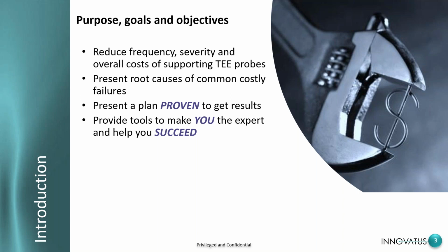So really our purpose here is to reduce the frequency, severity, and overall cost of supporting TEE probes. And that's key. So frequency, yeah, how many events do you have, but also severity. TEE probes have a wide range of damage when they come into Innovatus. At Innovatus, we repair literally thousands of TEE probes per year, and the damage can range from a broken locking knob to lock the probe into the system, all the way up to catastrophic failure. The insertion tube's been crushed and opened up, and fluid invasion. So we want to reduce not only the frequency, but the severity, which would lead to overall cost reduction of supporting probes.